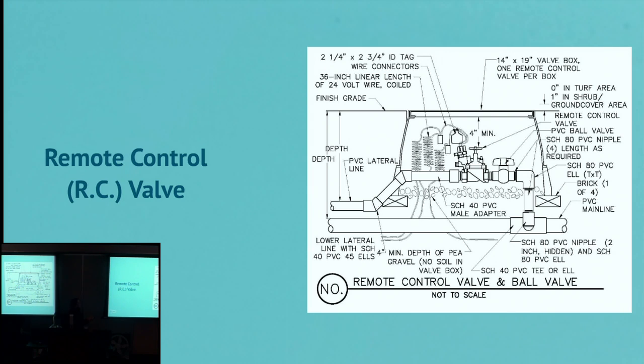The other thing that's important is the tag. Every single valve needs to have a tag, and on that tag it will be the controller designation and the station designation. So whenever you open up the cover, you know what station that valve is. Also, for reclaimed water, that tag needs to be purple. Anything that's reclaimed water, you have to have purple or lavender. With potable water, it can be yellow. And the wire connectors. The wire connectors are these little items right here. And those wire connectors need to be gel filled. Those little caps that screw onto wires to put the wires together are not allowed. They're not watertight. So look that you've got gel-filled wire connectors.